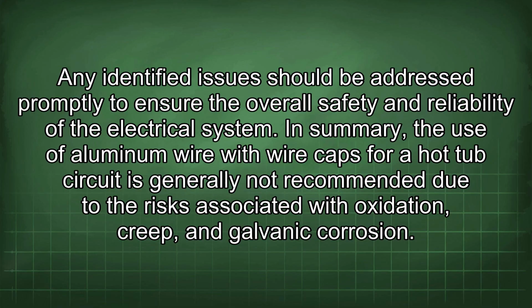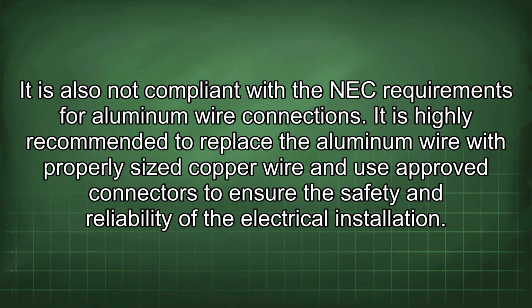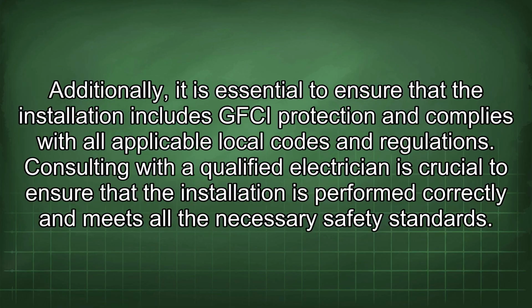In summary, the use of aluminum wire with wire caps for a hot tub circuit is generally not recommended due to the risks associated with oxidation, creep, and galvanic corrosion. It is also not compliant with the NEC requirements for aluminum wire connections. It is highly recommended to replace the aluminum wire with properly sized copper wire and use approved connectors to ensure the safety and reliability of the electrical installation. Additionally, it is essential to ensure that the installation includes GFCI protection and complies with all applicable local codes and regulations. Consulting with a qualified electrician is crucial to ensure that the installation is performed correctly and meets all the necessary safety standards.